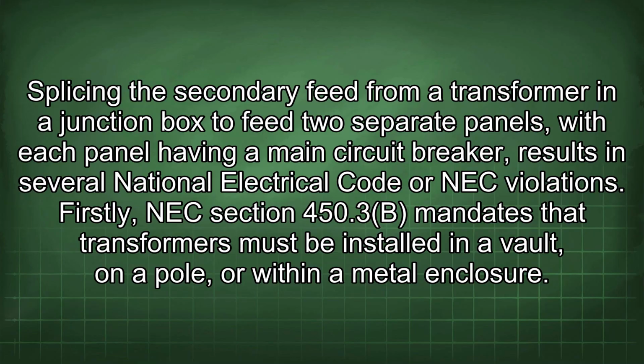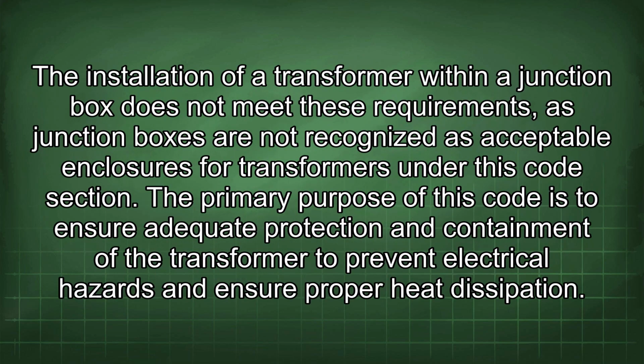Splicing the secondary feed from a transformer in a junction box to feed two separate panels, with each panel having a main circuit breaker, results in several National Electrical Code, or NEC, violations. Firstly, NEC Section 450.3(B) mandates that transformers must be installed in a vault, on a pole, or within a metal enclosure. The installation of a transformer within a junction box does not meet these requirements, as junction boxes are not recognized as acceptable enclosures for transformers under this code section.